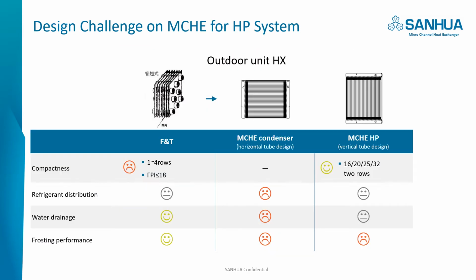Microchannel heat exchanger is typically used as a condenser in the cooling only unit with a horizontal tube design. But when it's used as an evaporator, it has difficulties with refrigerant distribution, water drainage, and frosting performance. SANHUA developed a proprietary heat pump with a vertical design. It achieved the compactness of a condenser, and also acceptable distribution and water drainage, but the frosting performance is not as good as a fin tube heat exchanger. These years, we are upgrading the design to achieve better distribution and better water drainage, but the frosting performance is still challenging for microchannel heat pump.